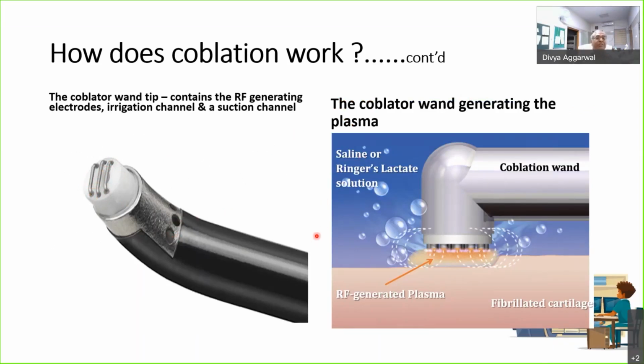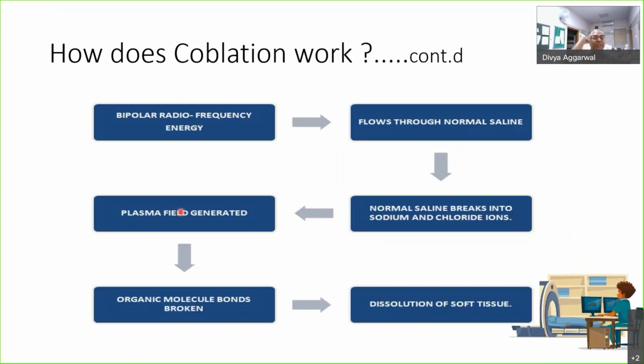So whenever you switch on the machine, you have to connect it to a saline bottle, and you have to connect the suction channel to a suction machine, a good suction machine. As soon as you switch on the machine, the radio frequency energy will be coming out of these electrodes, and at the same time the saline will be there in the field. So that this field does not get flooded with saline, otherwise your vision will be hampered, there is a suction also. So when there is saline and this radio frequency energy hits the saline, a sequence of events happens.